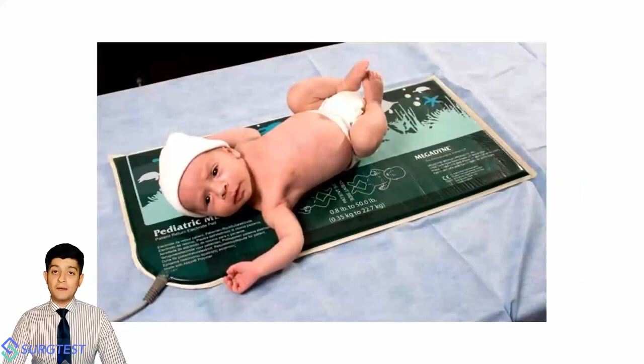Where is this pad particularly useful? It's amazingly useful in pediatric patients, where the entire child can be placed upon the pad. Note that in pediatric cases, surgeons otherwise usually use almost exclusively bipolar. But bipolar devices are by default not as flexible and don't allow as much manipulation of tissues as monopolar devices. Monopolar devices can be changed to get several different tissue effects. That's not the case with bipolar. So this is a very neat and safe way of using monopolar energy in a small patient.